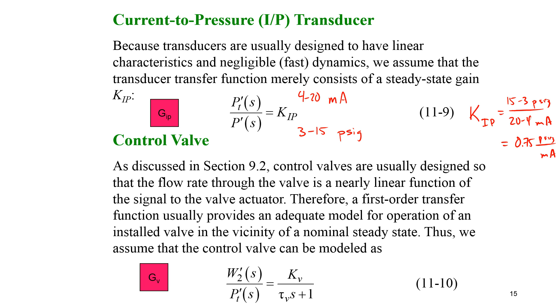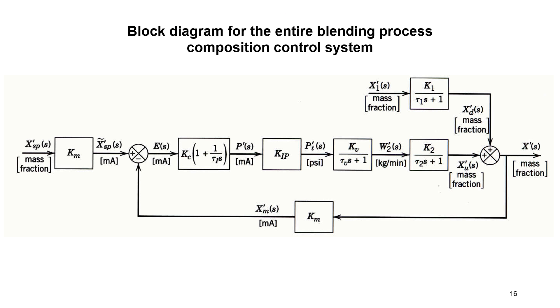We also have our control valve. If it's fast, we assume the time constant is zero. But not all control valves are fast, so we may need dynamics described by a first-order plus dead-time model. The gain relates a delta flow rate divided by delta PSIG, and the time constant is typically in units of time like seconds.